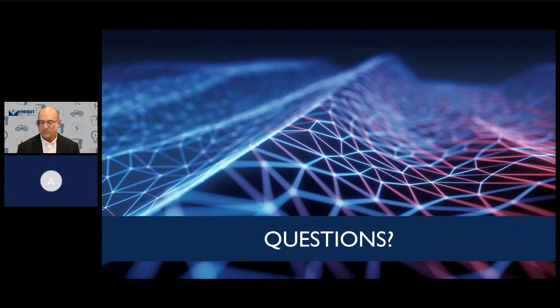Someone asked, what does a decimal point really do? How does it affect the output—like 0.999 versus 0.995? A good example: a lot of network administration contracts ask for 6 nines of uptime. If you calculate the ratio of hours on to hours available, 6 nines of availability equates to about 30 seconds of outage per year. As you start dropping nines, it's simple arithmetic, but it goes from 30 seconds to minutes to hours as you reduce your nines.